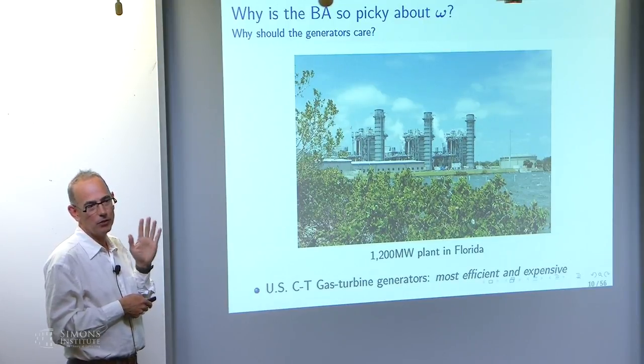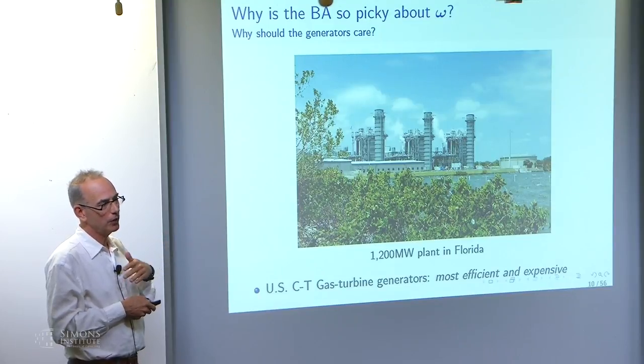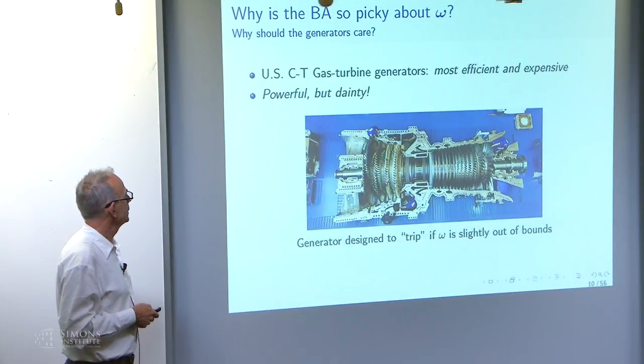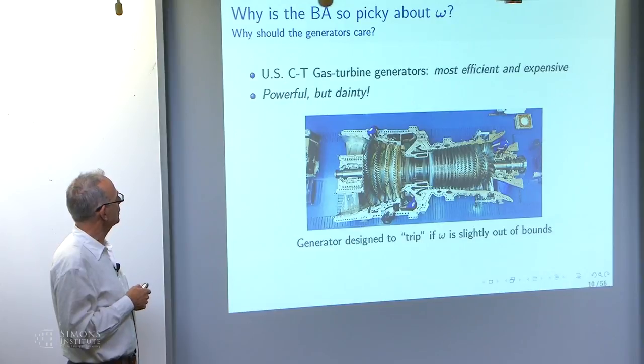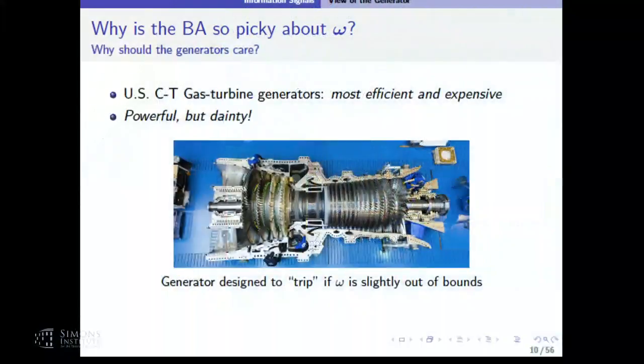So the most efficient generators are the most fragile. The combined cycle gas turbine generators are efficient, expensive, and dainty. They trip if the frequency goes out of bounds.